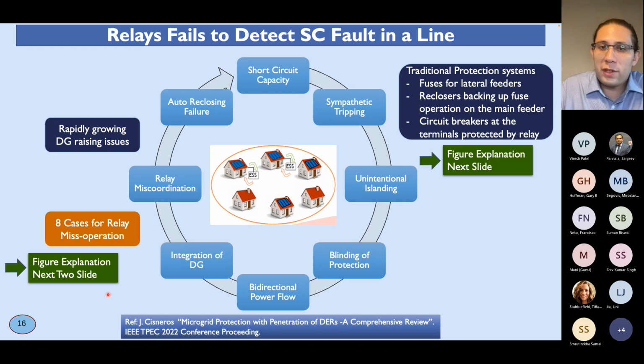We know that there is traditional protection, which consists of different fuses, reclosers, and circuit breakers. But in the industry, with the implementation of so many energy resources, renewable energy generation on the load side, we do have these common cases that were identified in the paper we presented before with the IITBBS group, as part of this project. We identified short circuit capacity, sympathetic trip, unintentional islanding, blinding of protection, bidirectional power flow, integration of another DG, relay miscoordination, and finally the auto-reclosing failure mode. These are 8 cases that we could identify after a very extensive literature review, and find in the books, compared to how protection was used traditionally.